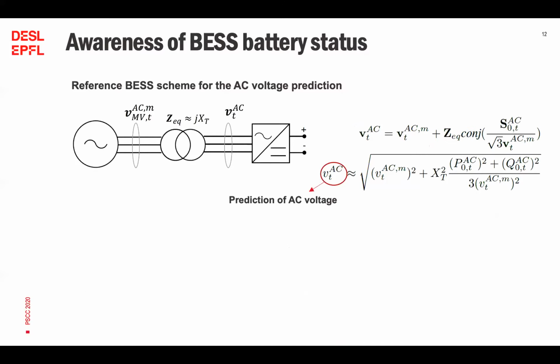The prediction of the AC voltage at the low voltage side of the step-up transformer of the BESS system is obtained by approximating the equivalent impedance with the reactance of the transformer itself. The approximation, in fact, is motivated by the fact that the rated power of the step-up transformer of our installation is 720 kilovolt ampere and is way lower than the rated power of the campus transformer that links the campus to the main medium voltage utility grid.